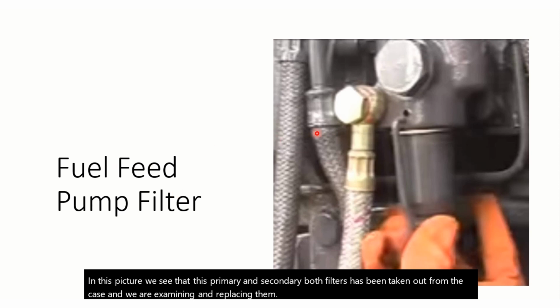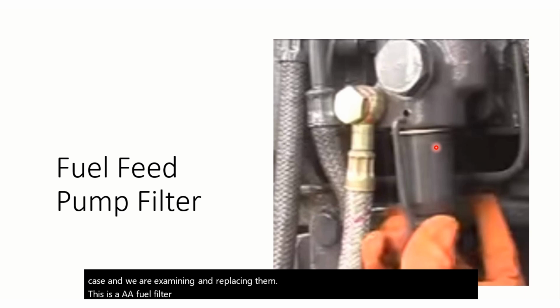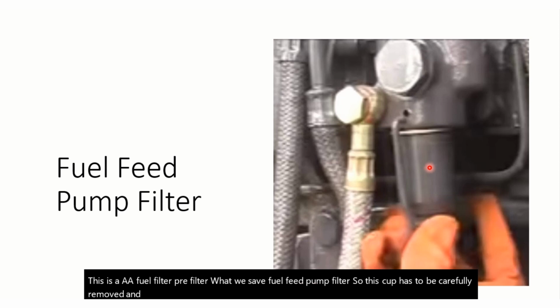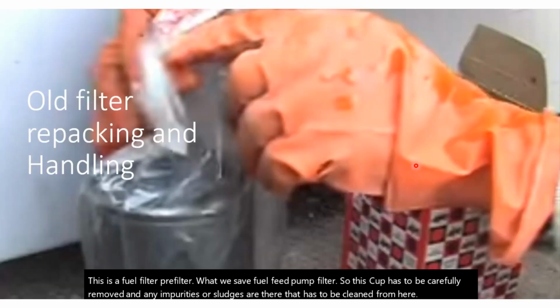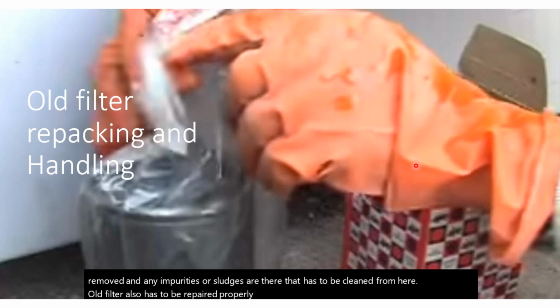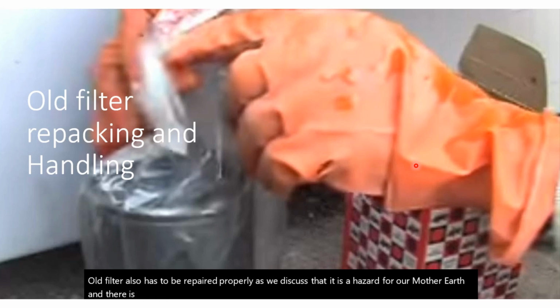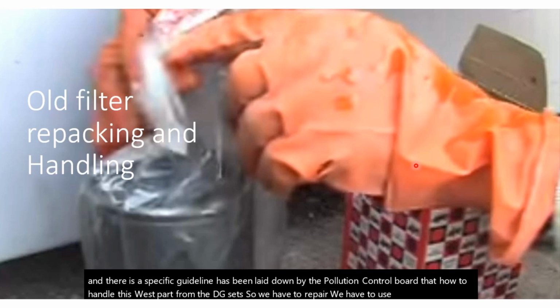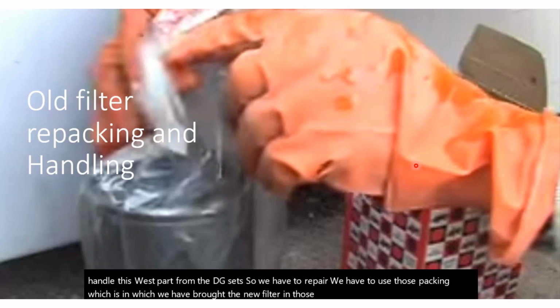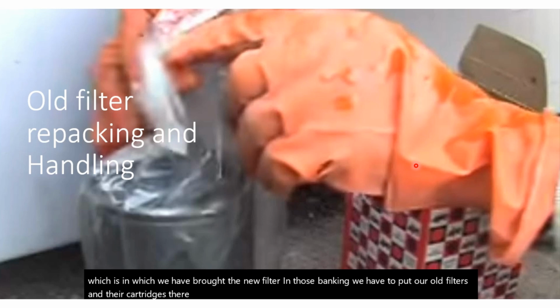This is a fuel pre-filter, what we call the fuel feed pump filter. So this cup has to be carefully removed, and any impurities or sludge has to be cleaned from here. The old filter also has to be repacked properly, as we discussed, since it is a hazard for our mother earth, and there is a specific guideline laid down by the pollution control board on how to handle this waste part from the DG sets. So we have to use the packing in which we brought the new filter, put our old filters and their cartridges, their elements back in it, and then handle this as per our waste management policy.